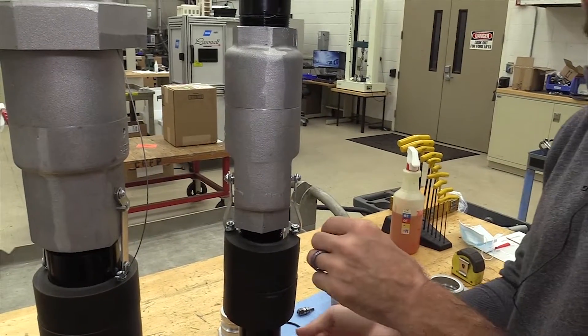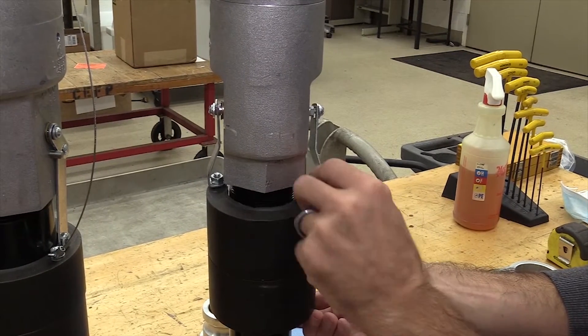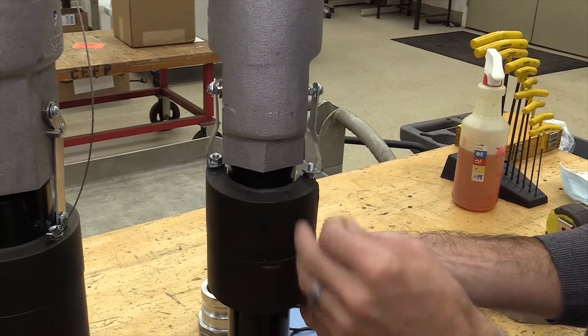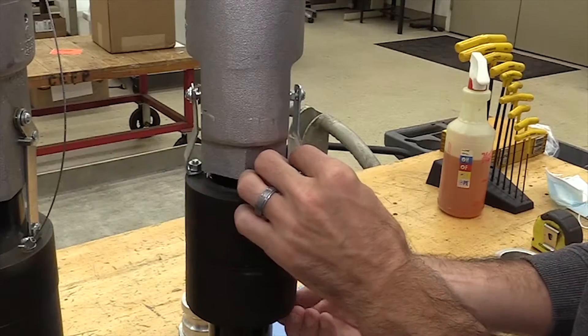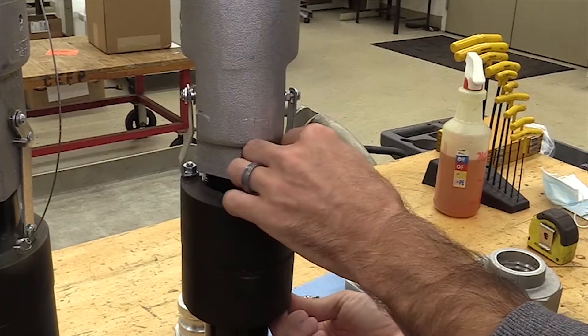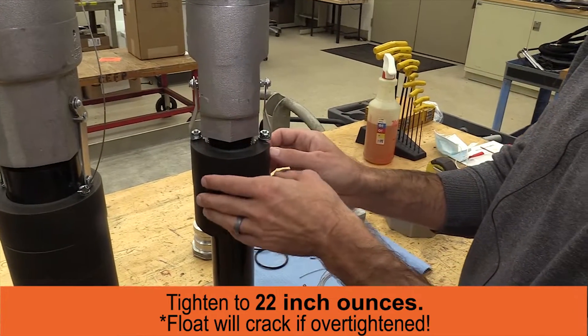After that, you need to remove one of the nuts from the float. For the half float such as this, you can remove any nut as long as the cable connector is pointed back towards the float. Once that's put on, you can reconnect the nut. These can be tightened down to 22 inch-ounces. Make sure you do not over-tighten it — it will crack the float.